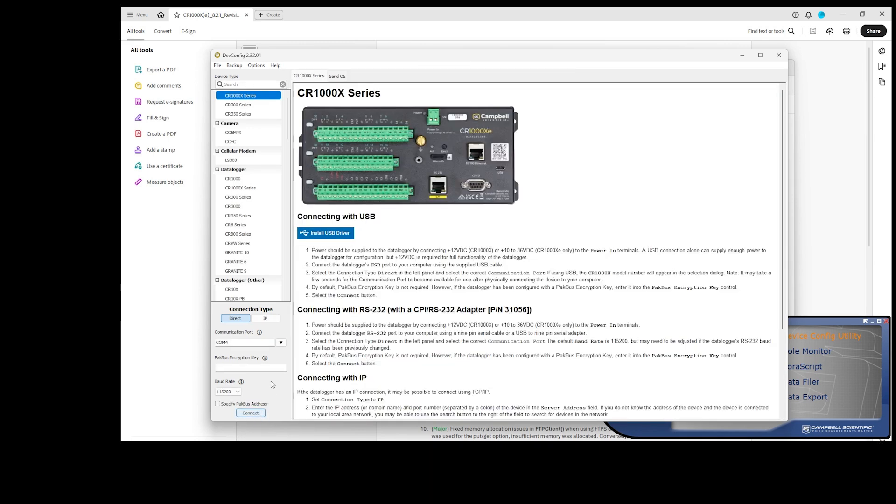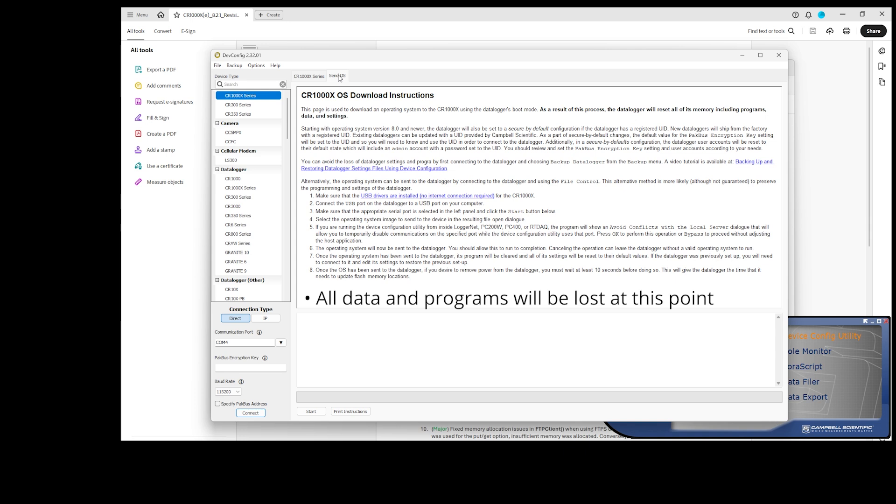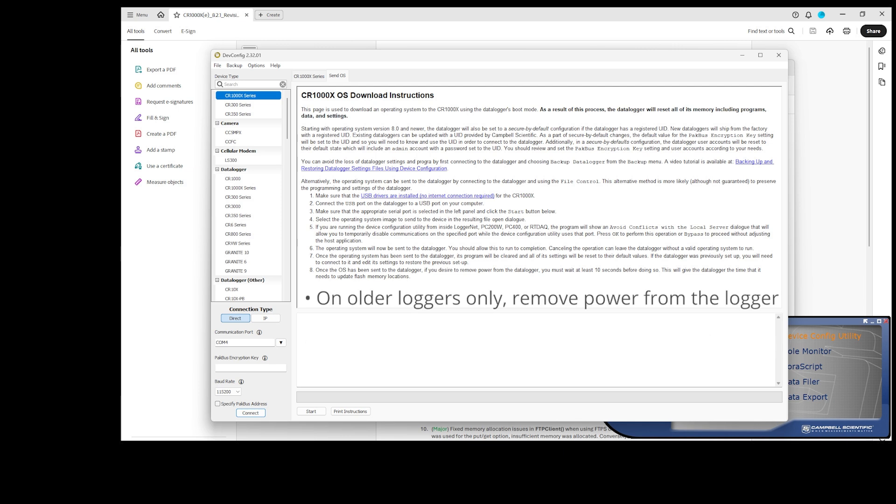Now that my data logger is backed up, I can go back to the Send OS tab. All data and programs will be lost at this point. The data logger will be set back to factory default. For older CRBasic data loggers, such as the CR1000 or CR3000, I would need to remove power from the logger. Not cycling power for these older loggers is one of the most common errors people make.